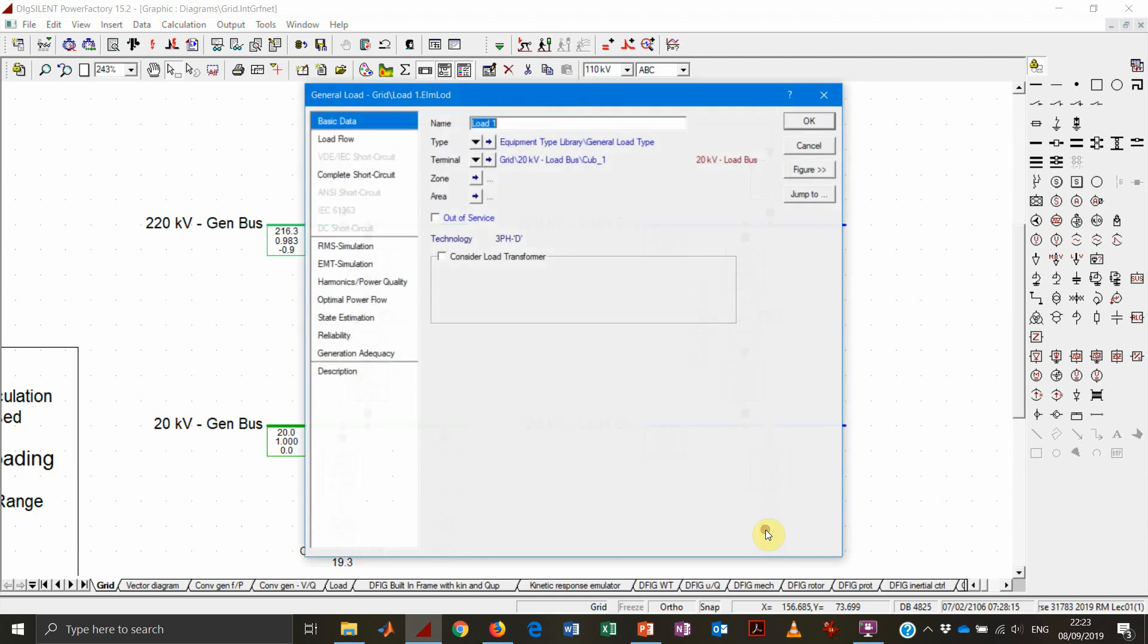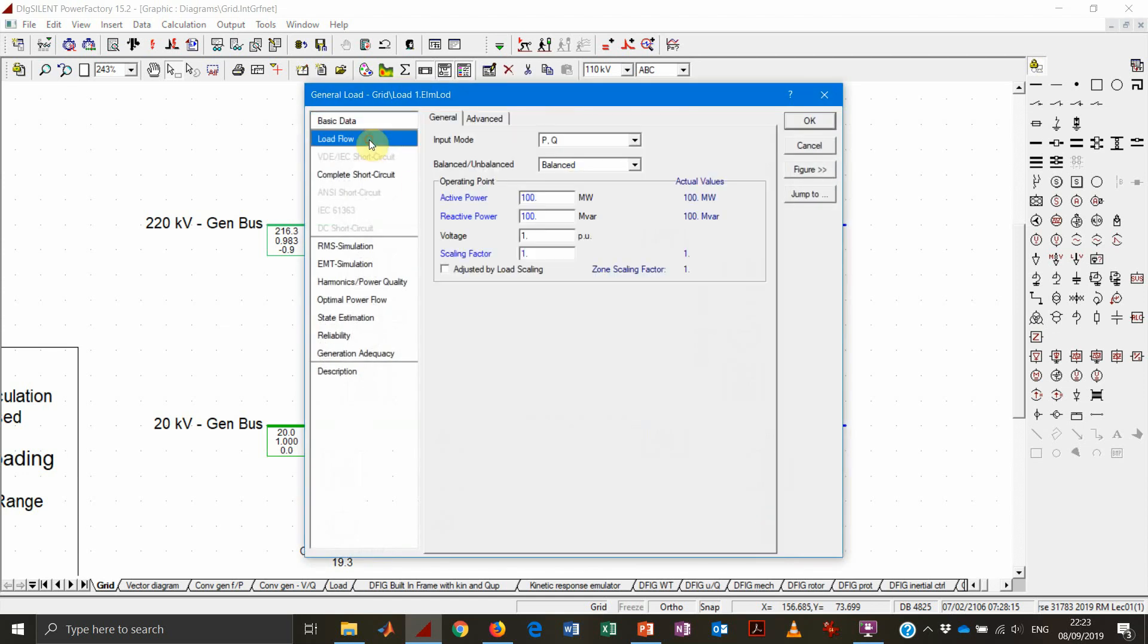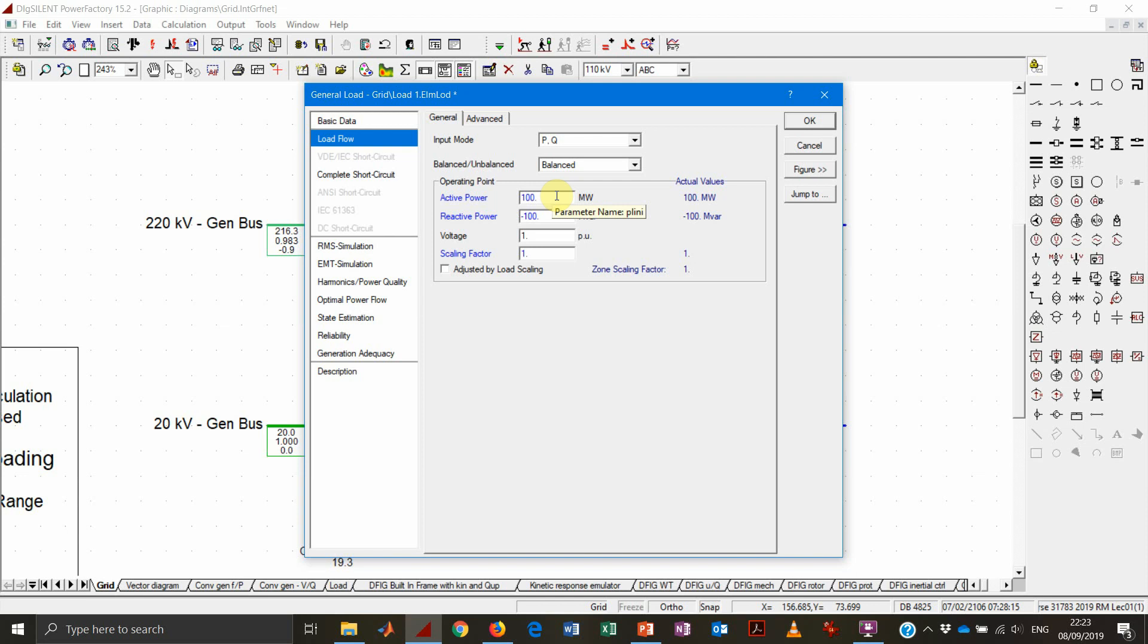The same will apply also if we switch to capacitive consumption or capacitive production for the reactive power. As always, remember that power factor is following this convention: for loads, it will be used in the load convention, so positive active power implies consumption, while positive reactive power implies inductive behavior, and negative reactive power is capacitive behavior.